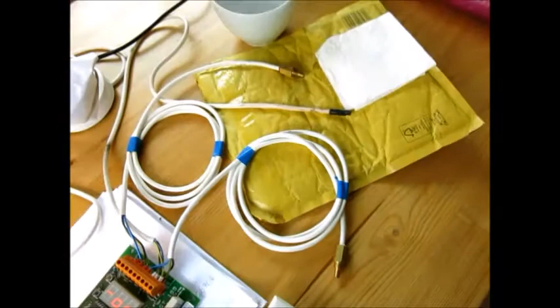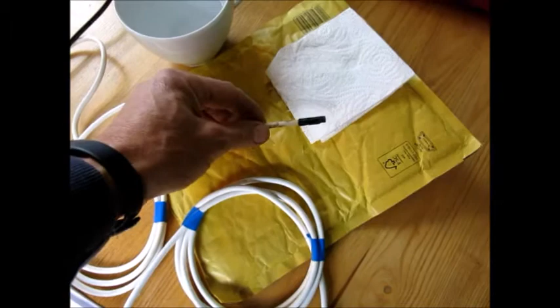What happens is the boiler is heating the heat store. This thermocouple, thermistor - it's actually a digital thermistor - is in the heat store and will monitor the temperature in there. This thermistor is the one found at the top of the plate heat exchanger, the one that converts the heat store hot water into hot water for the taps, etc.